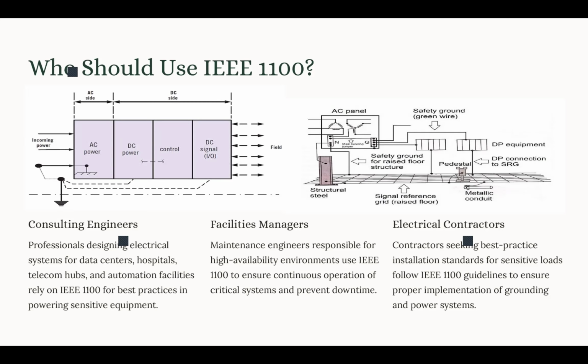They have to make sure they have proper grounding and bonding, and that the conduits and cable layouts are based on the requirements. For example, they use twisted pair or shielded conductors for long runs, or run hot, neutral, and ground conductors together in the same conduit, so they can reduce inductive noise coupling. These are the situations when we talk about implementing those designs. These electrical contractors have to make sure they're following the IEEE 1100 recommendations. If they don't, they affect the design. They can nullify the entire functional grounding strategy and lead to logic faults or equipment damage.